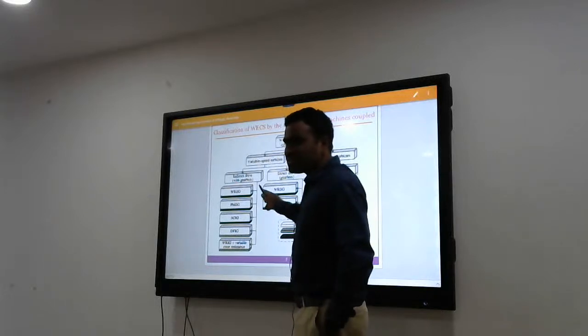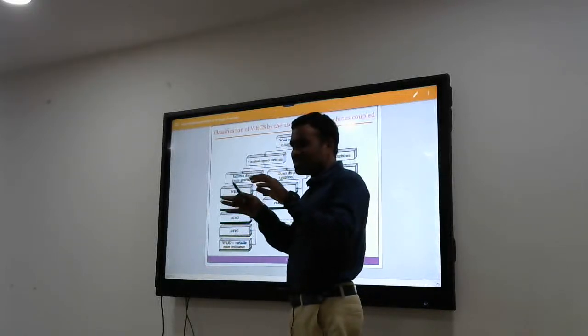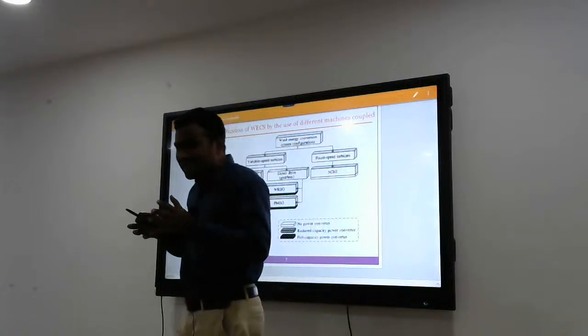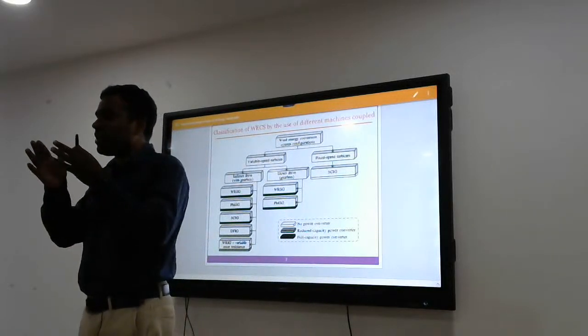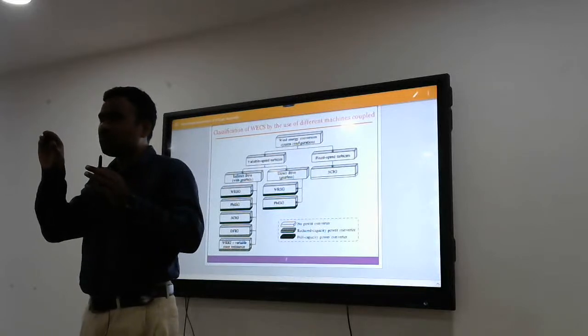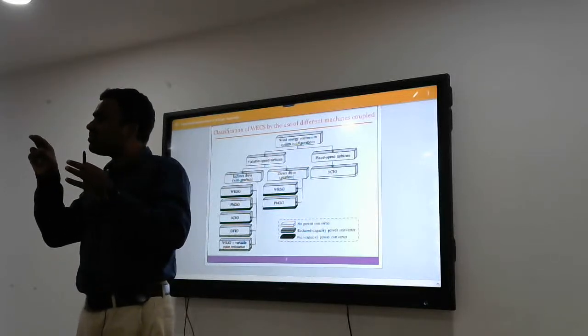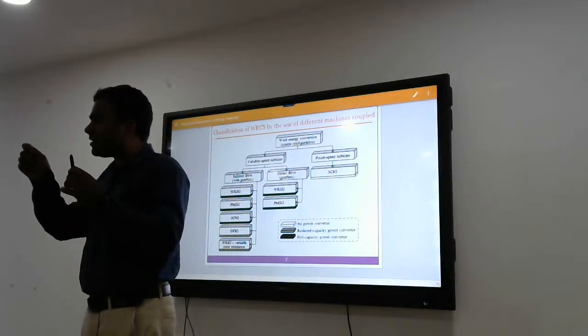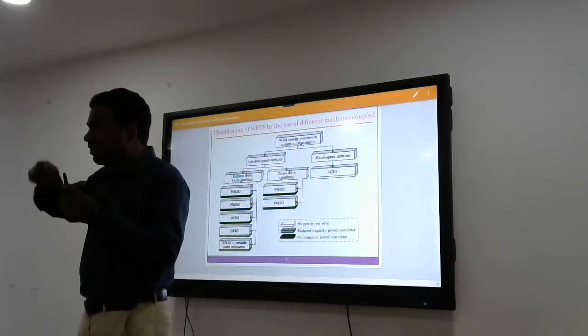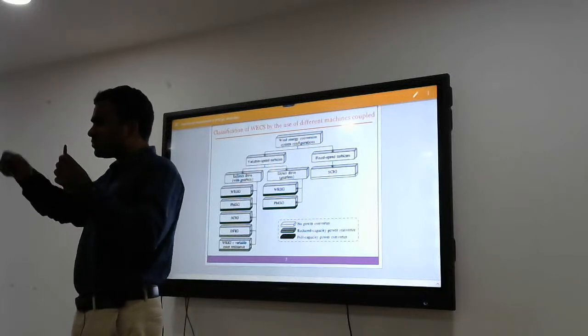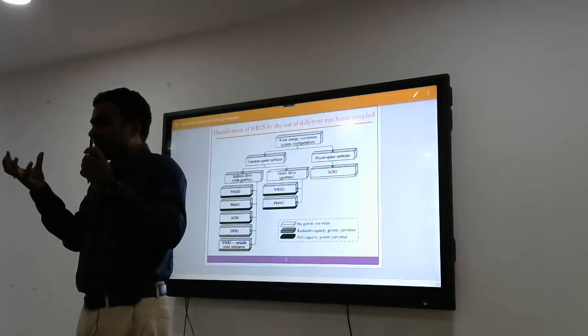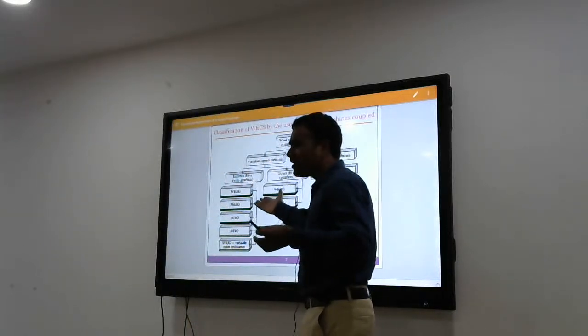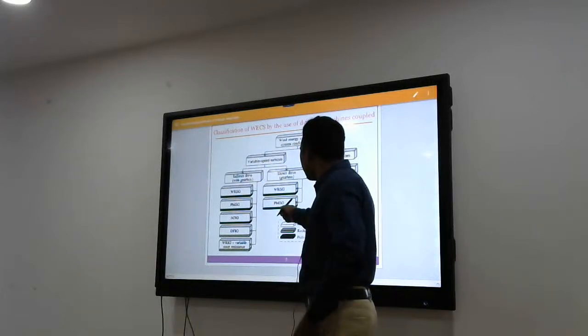In all machines that is not possible, but in permanent magnet synchronous machines, you will have freedom to increase the number of poles, because if you have permanent magnets, maybe they can be fit in. But if you have wound rotors, to get the same poles using electromagnets, you need to wind coils on some magnetic material, and that needs more space. So normally in a PMSG you can increase the number of poles, but in other machines that's not possible.